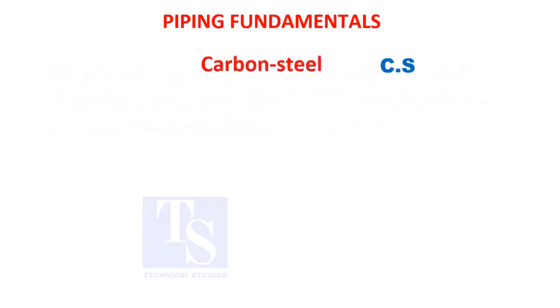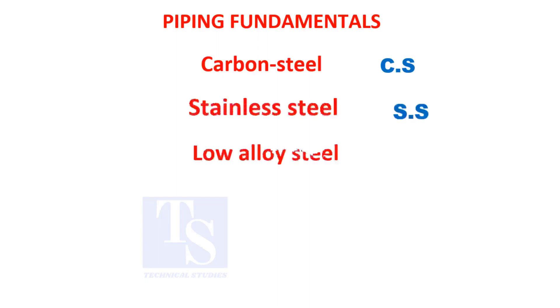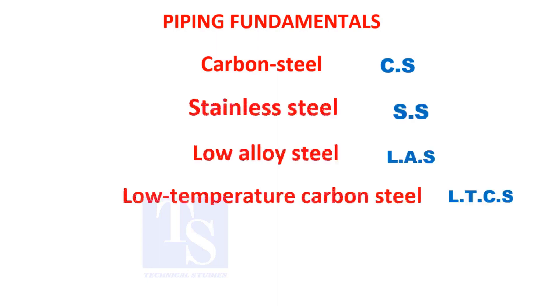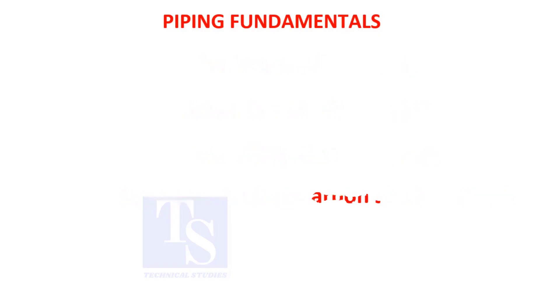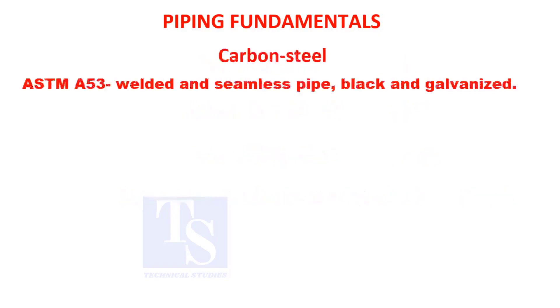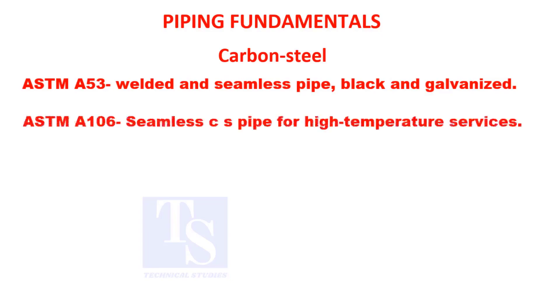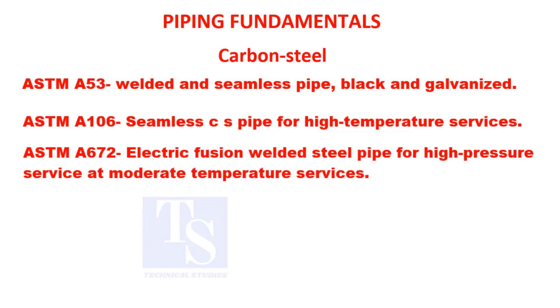Generally used piping materials are carbon steel, stainless steel, low alloy steel, and low temperature carbon steel. ASTM A-53: welded and seamless pipe, black and galvanized. ASTM A-106: seamless CS pipe for high temperature services. ASTM A-672: electric fusion welded steel pipe for high pressure and moderate temperature services.